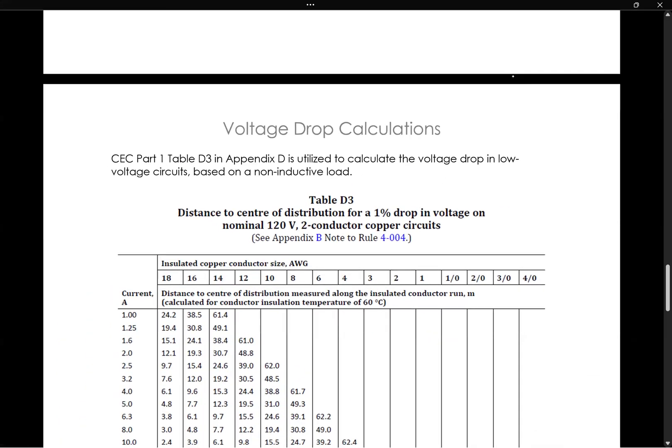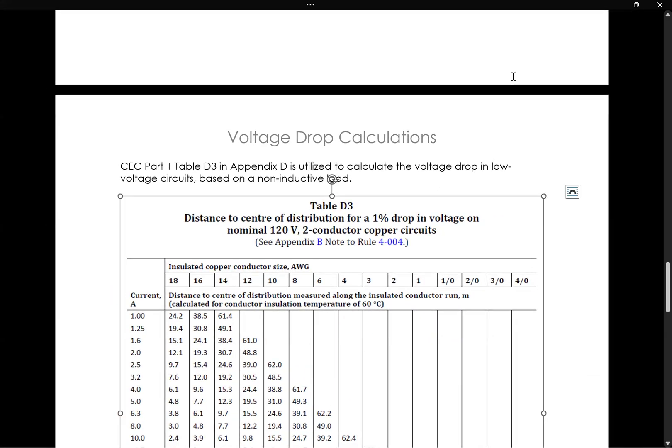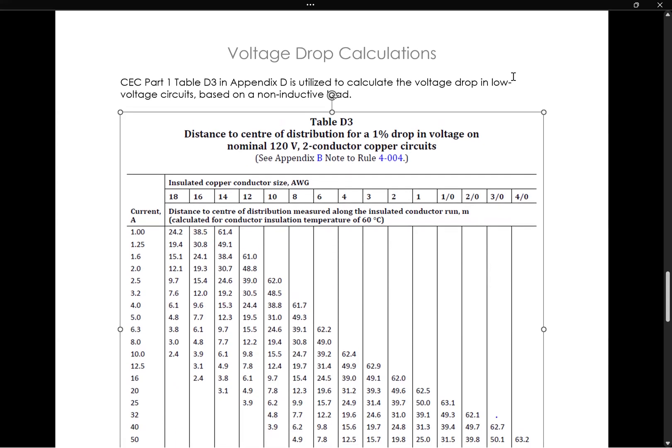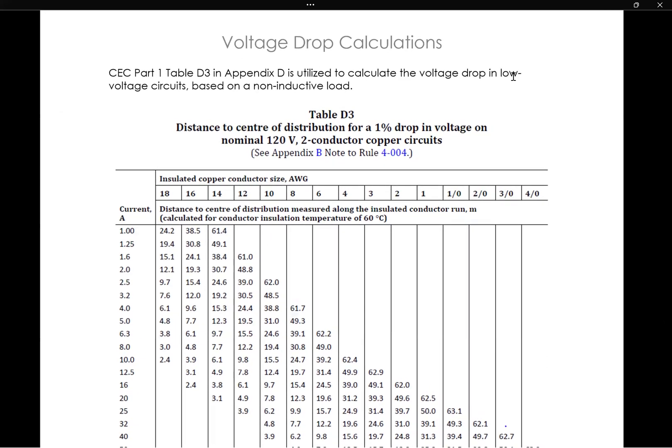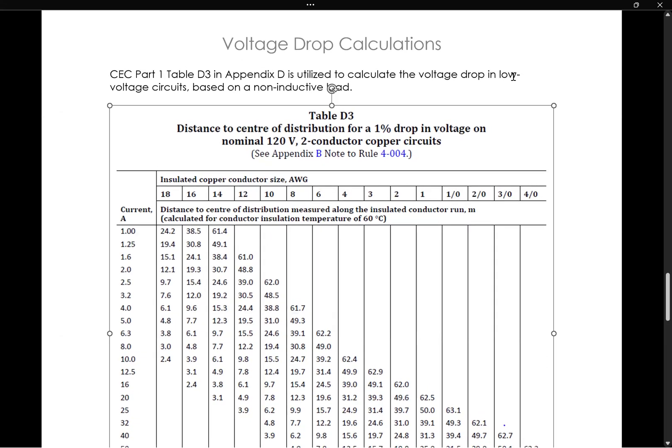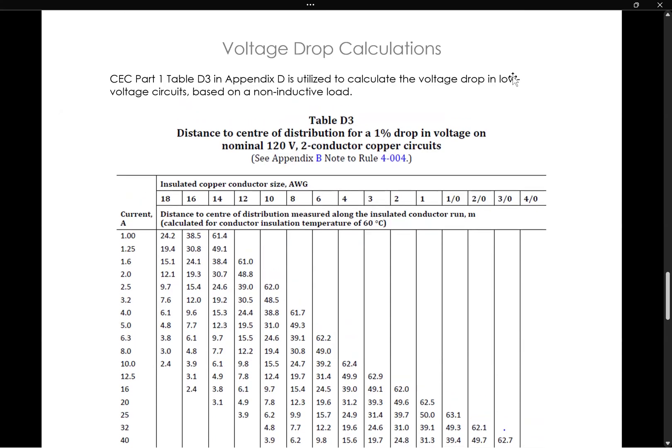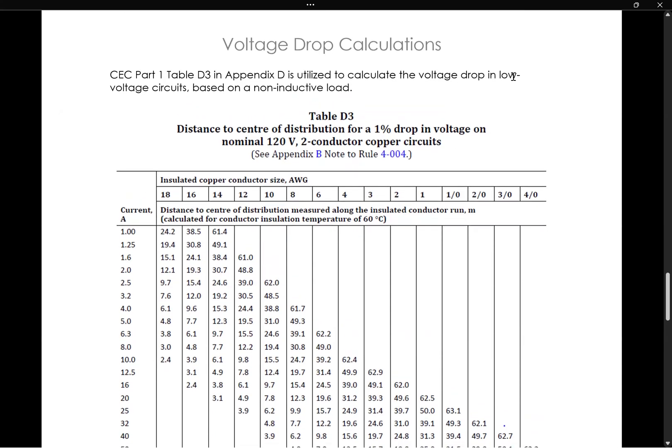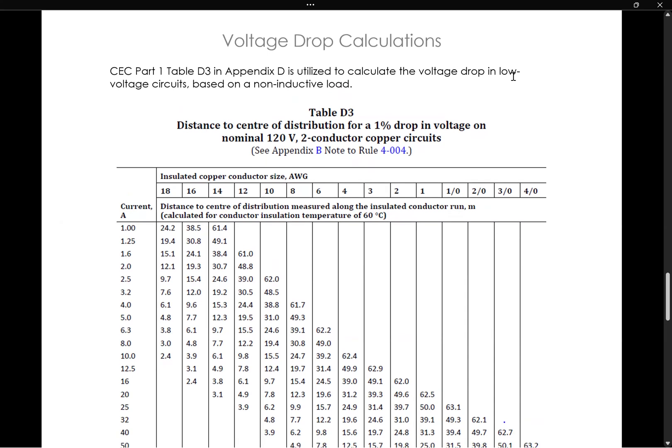So of course our Canadian Electrical Code doesn't have our tables sitting right there in the code. The tables sit in sections that include all of the tables. Appendix D is one of those sections that has all of the tables. And this particular table that is going to apply to rule 8-102 about voltage drop is called table D3 that we know and love. And so that's the table that is used to calculate the voltage drop in low voltage circuits based on non-inductive loads.